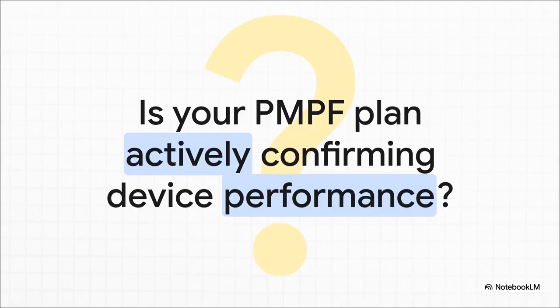And all of this data you're collecting feeds into something called your Post-Market Performance Follow-Up Plan, your PMPF. Let's be really clear here. This is not just about sitting back and waiting for complaint calls to come in. No way. This is about proactively going out and collecting real-world data to confirm that your device is still safe and performing exactly the way you said it would. So you have to ask yourself, is your PMPF plan an active, living process, or is it just another document collecting dust on a shelf?